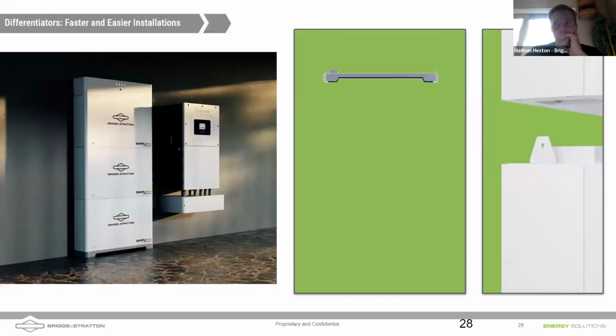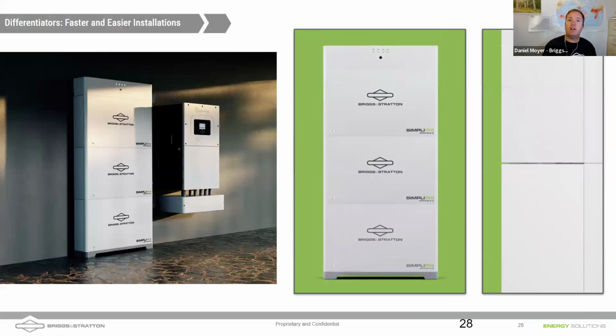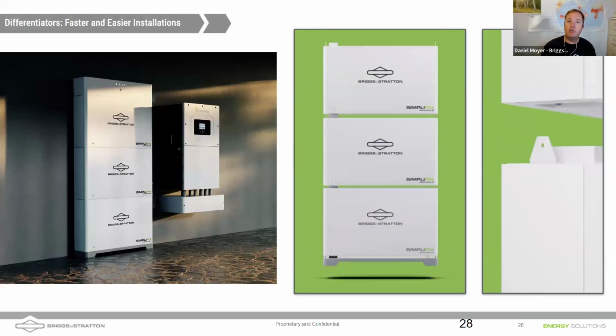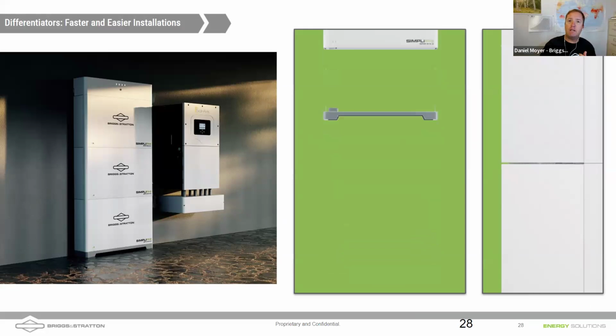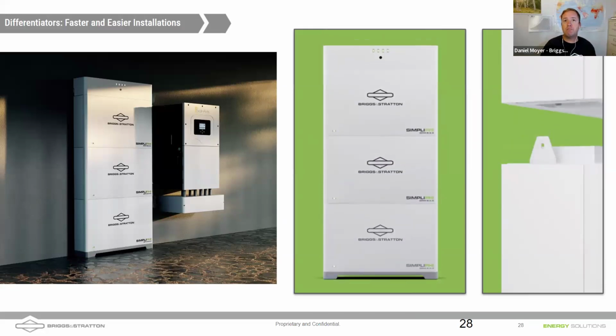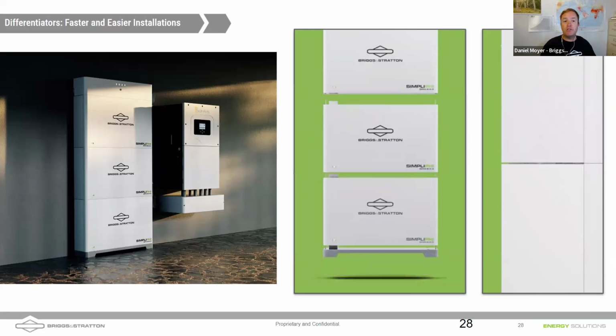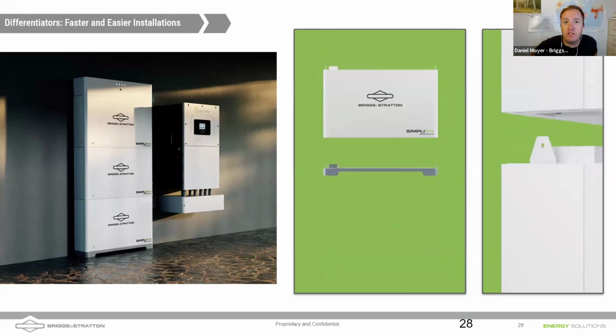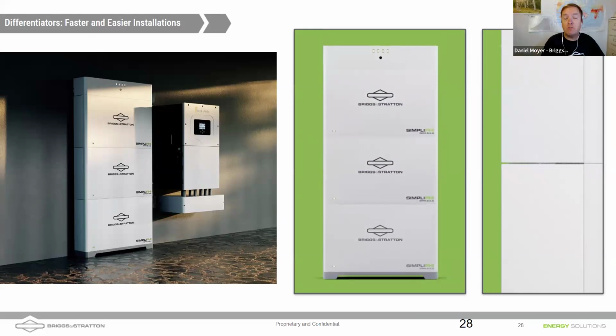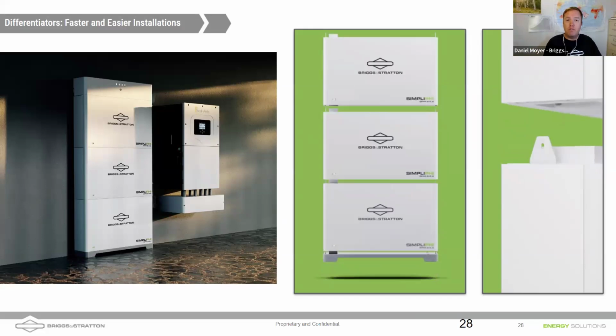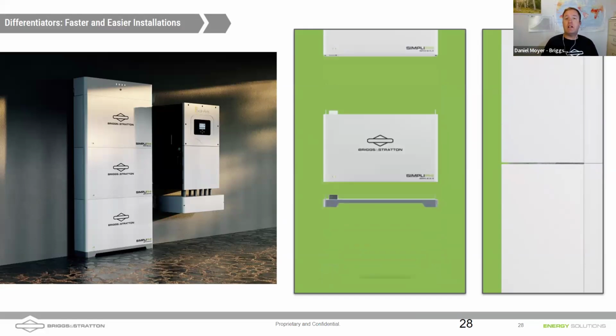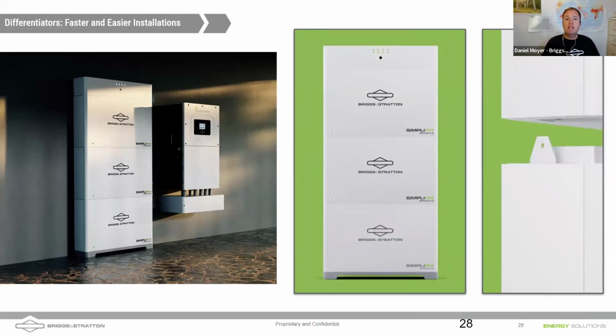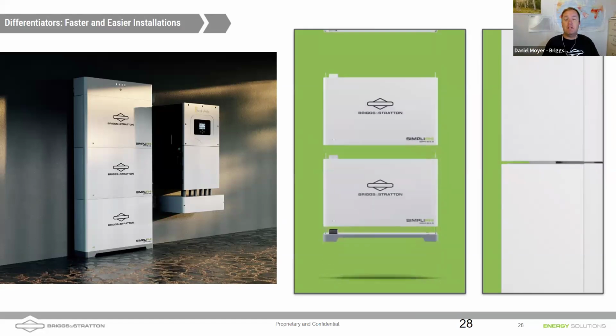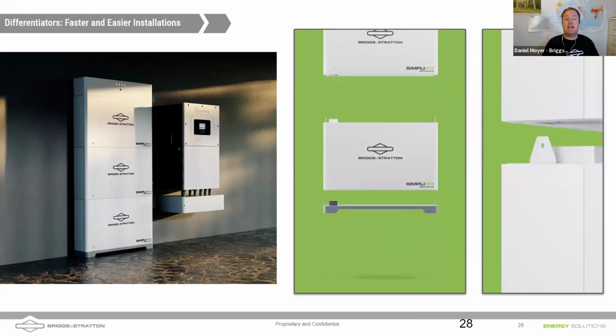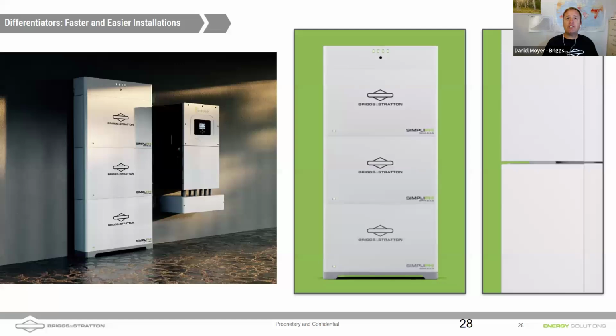Let's jump into some of our products here. One of our exciting new products is our new stacking 6.6 battery. Each one of these modules is 6.6 kilowatt hours. So you're seeing a stack that comes in just under 20 kilowatt hours. That was intentional to meet some of the NFPA standards when it comes to building and fire codes.